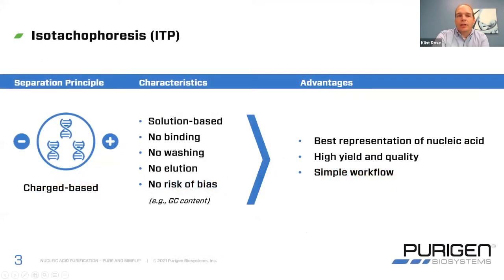Let me explain isotachophoresis — this is the core technology that we have developed around. Isotachyphoresis, or ITP, uses charge as the primary separation principle. We're taking advantage of the key attributes of nucleic acid, which is that it is both highly charged and its speed in an electric field is actually independent of its length. So no matter whether you have short DNA, short RNA, long DNA, or long RNA, they all move at the same speed in free solution. The characteristics we get from that is that all extractions are solution-based — we're not binding to a surface, therefore we're not needing to wash, and there's no elution process. The benefits this gives us are no risk of bias, as well as the best representation of the nucleic acid.